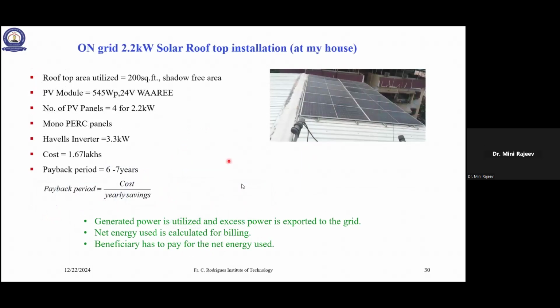This is an example of an on-grid 2.2 kilowatt solar rooftop installation. This is done at my house. Rooftop area utilized is 200 square feet, shadow-free area. The PV module we have used is 545 watt peak, 24 volt. Number of PV panels: there were 4 for 2.2 kilowatt, that is 2.2 kilowatt divided by 545.